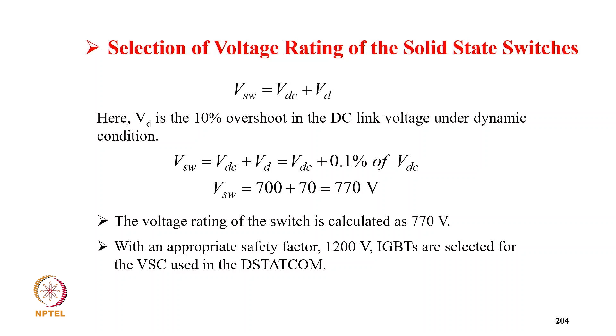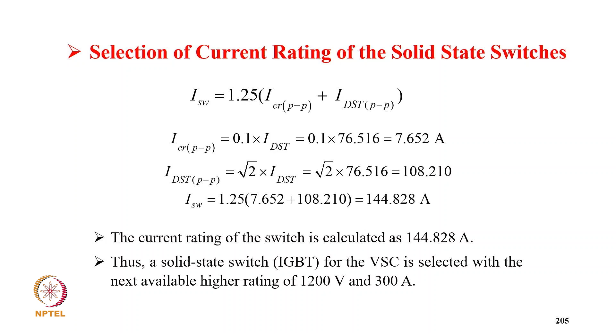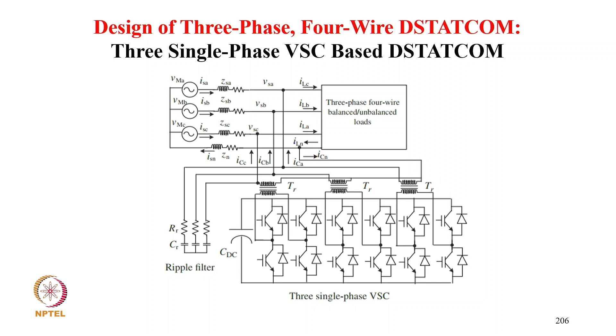Now coming to current rating selection, ISW equals 1.25 times (ICR plus ID STATCOM). So putting the value, ICR comes 7.652 ampere, and the switch current is typically the sum of both, so it comes 144.828 ampere. So the current rating of the switch is calculated as 144 ampere, and then the solid state switch for VSC is selected with the next higher rating of 1200 volt and 300 ampere. So this is typically the design of a three-phase 4-wire DSTATCOM with three single-phase voltage source converters.